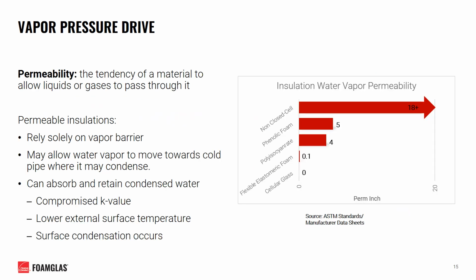When determining the right insulation material for your chilled water system, one property you may want to consider is the permeability of that insulation material. Permeability is the tendency of a material to allow liquids or gases to pass through it. Permeable insulations rely solely on the performance of an external vapor barrier to keep water vapor out of a system. If that vapor barrier becomes compromised, permeable insulations can allow water vapor to move towards the cold pipe where it may condense along the surface.